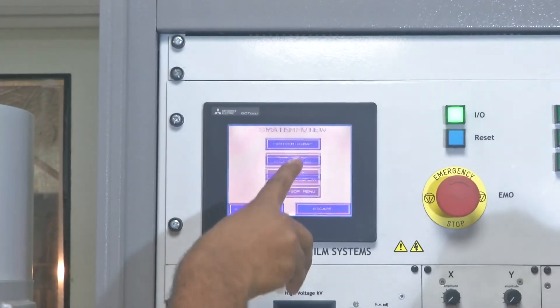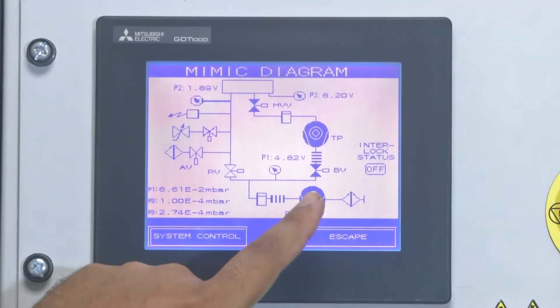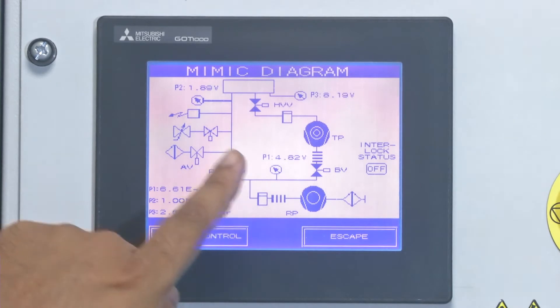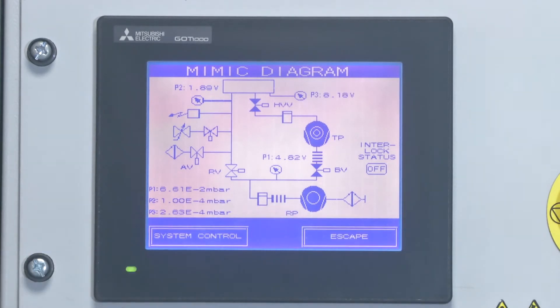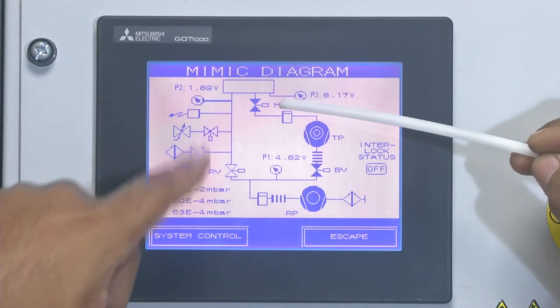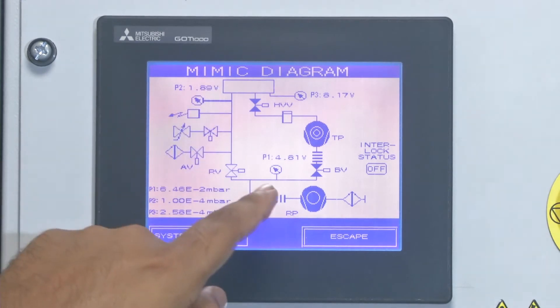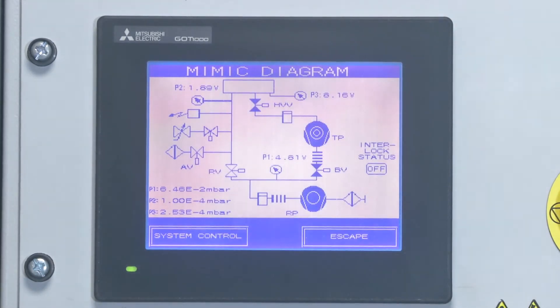If you want to see the readings of all three gauges, go to system live view. You can see the entire structure of the system — all the different valves, limit switches, high vacuum valve, turbo pump, gate valve. Whichever is shown in blue means those valves are on and working; others are not on. Right now the roughing valve is on. This is the initial pumping process.